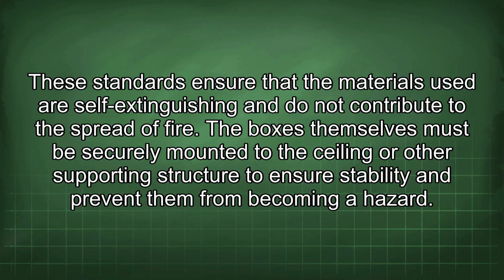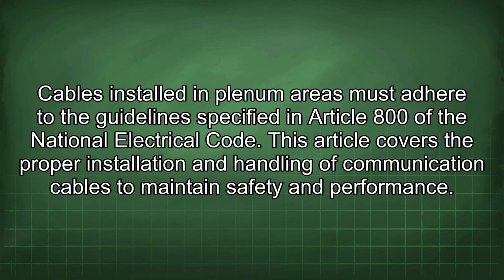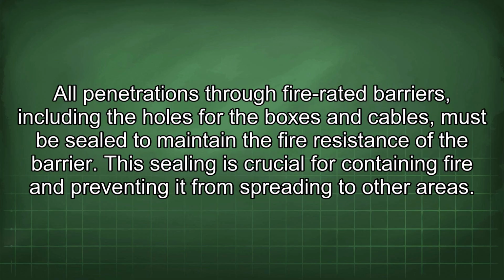from becoming a hazard. Cables installed in plenum areas must adhere to the guidelines specified in Article 800 of the National Electrical Code. This article covers the proper installation and handling of communication cables to maintain safety and performance. All penetrations through fire-rated barriers, including the holes for the boxes and cables, must be sealed to maintain the fire resistance of the barrier. This sealing is crucial for containing fire and preventing it from spreading to other areas.